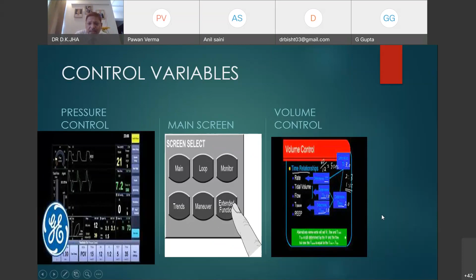There is an extended quality test before starting the ventilation. You press the button, and the ventilator will check everything, such as pressure leak and oxygen. If everything is passed, then only is the ventilator ready for operation. So this is just to be acquainted. This is the pressure control mode of ventilation. We control PIP, PEEP, and rate, and this is the volume control. We set the rate, tidal volume, PEEP, inspiratory time and flow in this. So just be acquainted with this.